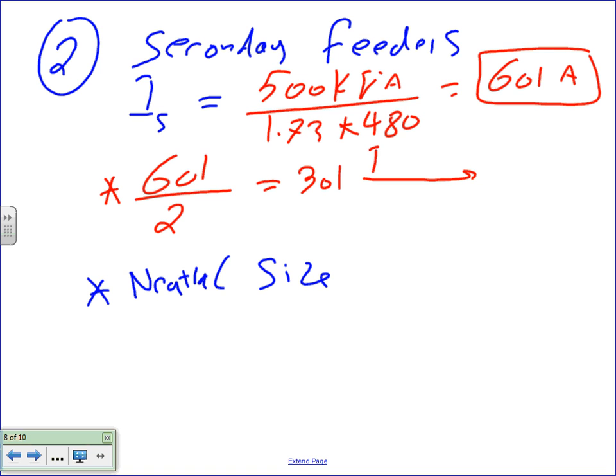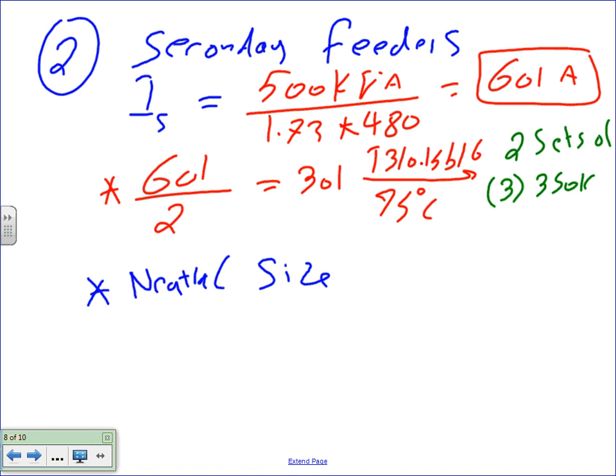And if you go to table 310.15(B)(16) under the 75 degree column, that will get you the following. Two sets of the conductors that I have, two sets of three conductors. Each one of them is 350 KCM this time, THHN. Two sets of 350 KCM conductors. We're paralleling. Any questions about that? Piece of cake, huh?